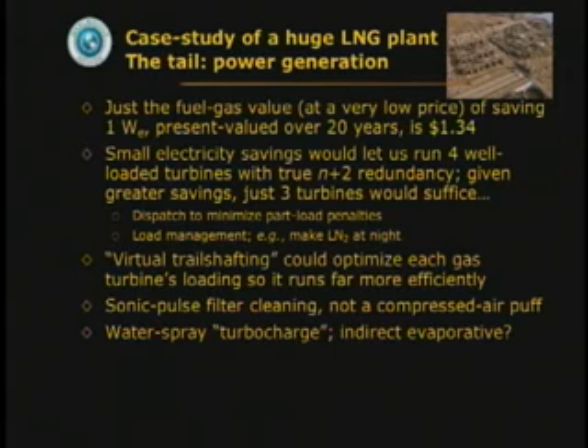You can turbocharge your gas turbines with water spray and with evaporative cooling. Remember, they're optimized to run at 40,000 feet in an airplane where it's real cold, not at 54 C in a blazing desert. Better still, use combined cycle, which is a lot more efficient, about twice as efficient as what they've got. And there are some renewables that could be useful at that site.